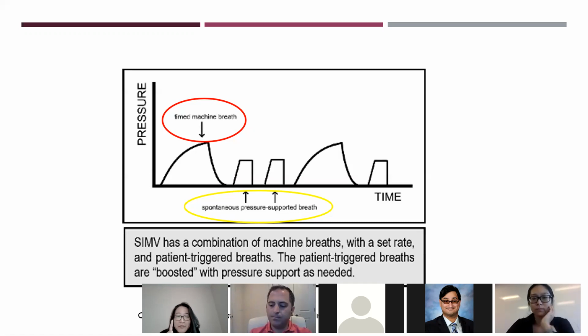Okay, so just to clarify, if the patient were to become tachypneic, the machine would still do its own calculations and try to give both types instead of just converting all the way to pressure support. Yes, but it does depend on the machine and the model. It does it not over the whole minute but over shorter spans of time. So it looks at the last 15 seconds or 10 seconds, and it continually averages.